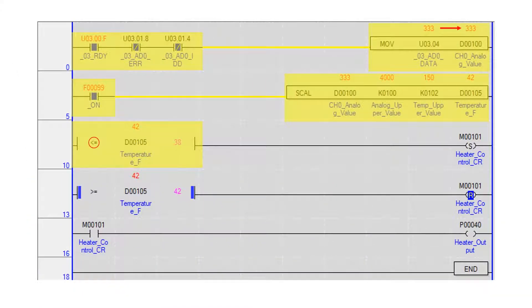Using a less than or equal to compare instruction, the current temperature is compared to a set point of 38. If the temperature is at or below 38 degrees, the internal bit heater control CR is set.